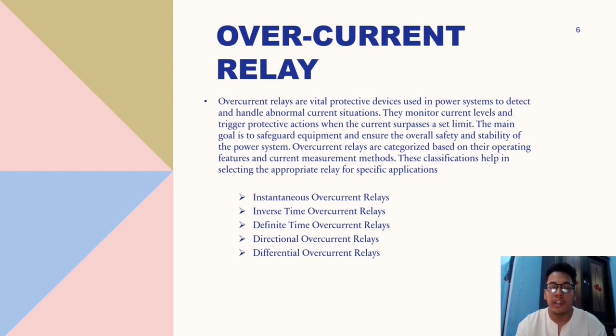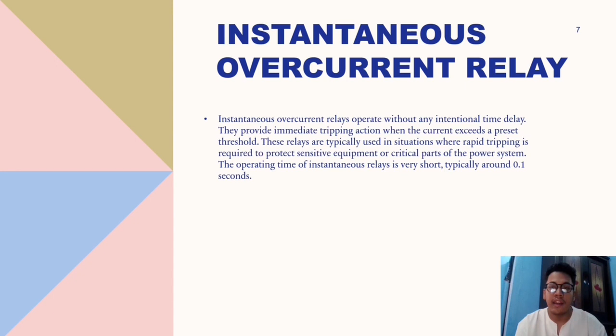So we can see there are 5 type of overcurrent relay, which is instantaneous overcurrent relay, inverse time overcurrent relay, definite time overcurrent relay, directional overcurrent relay, and differential overcurrent relay. Instantaneous overcurrent relay operate without any intentional time delay. They provide immediate tripping action when the current exceeds a preset threshold. These relays are typically used in situations where rapid tripping is required to protect sensitive equipment or critical part of the power system. The operating time of instantaneous relay is very short, typically around 0.1 second.